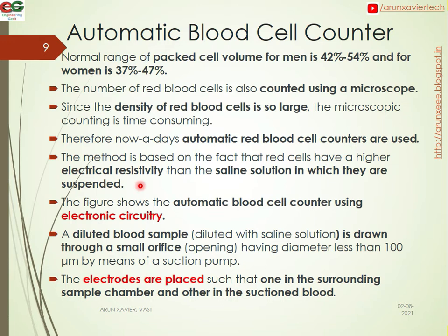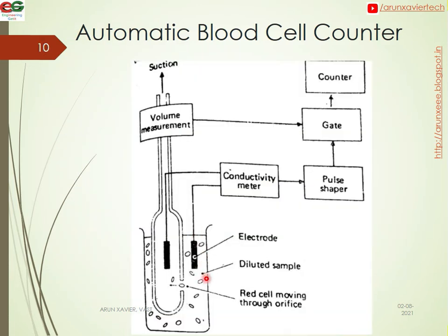The figure shows the automatic red blood cell counting system using an electronic circuit. The diluted blood sample is drawn through a small orifice into a counting channel. We are using two electrodes here to measure conductivity. The resistivity changes as red blood cells pass through, allowing us to count them automatically.